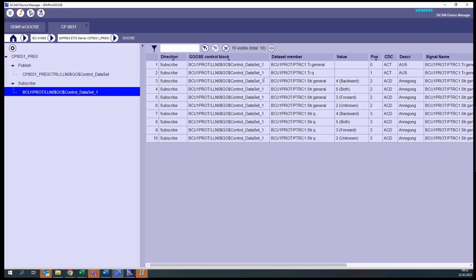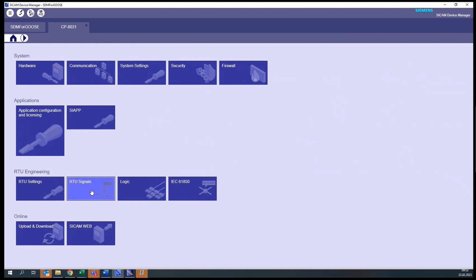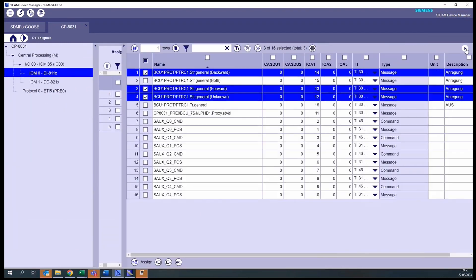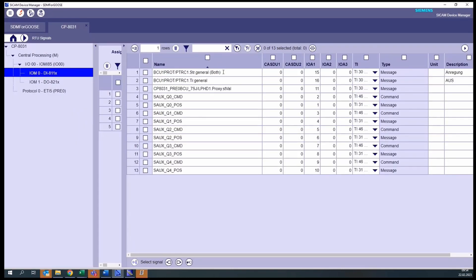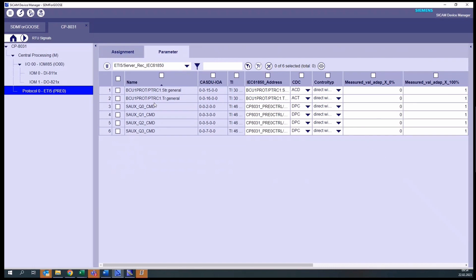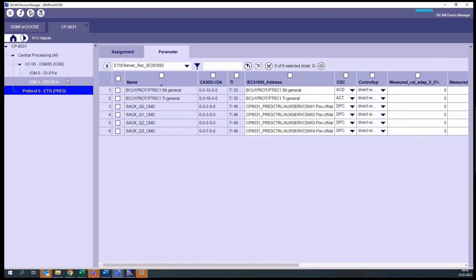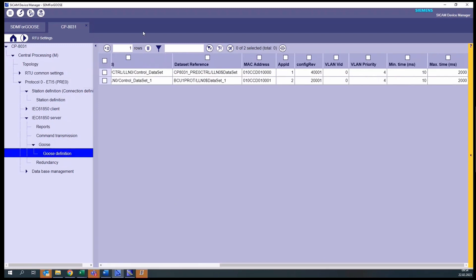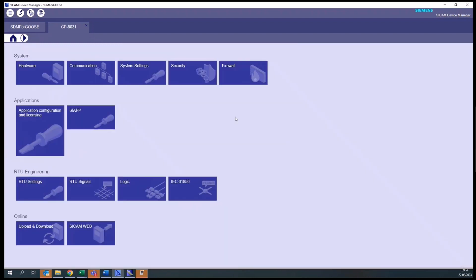Maybe we are not interested in having all of them, so if that is the case, we can just come here in Signals and delete them. We will change the name and that's it. You can see in the configuration of the CP8031 in the Signals that it has receiving direction. The trips are shown here with the proper address, and you can check in the RTU Settings that for both we are receiving these data sets. Basically, this is how you can configure GOOSE communication in the SICAM A8000. I hope you enjoyed this video — we will be publishing more videos soon.